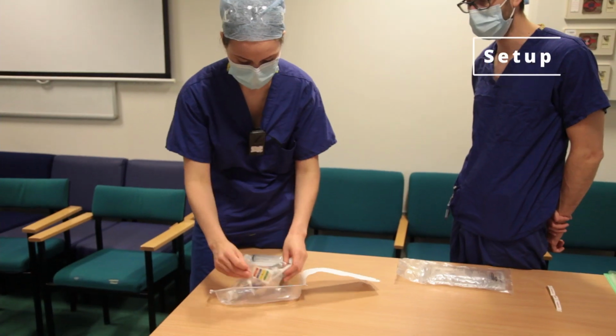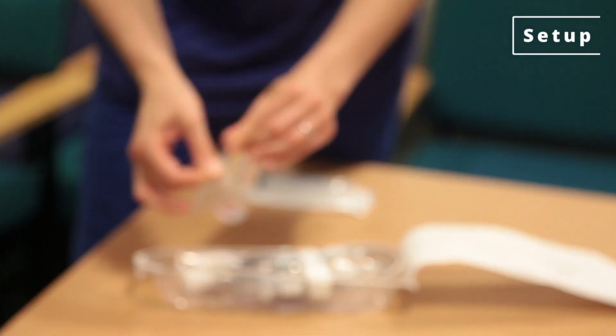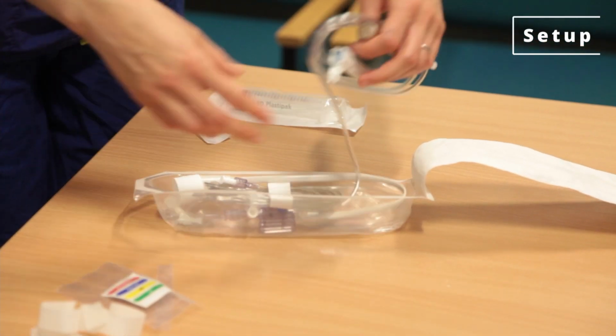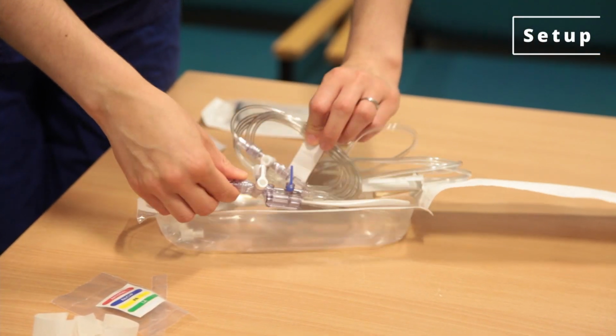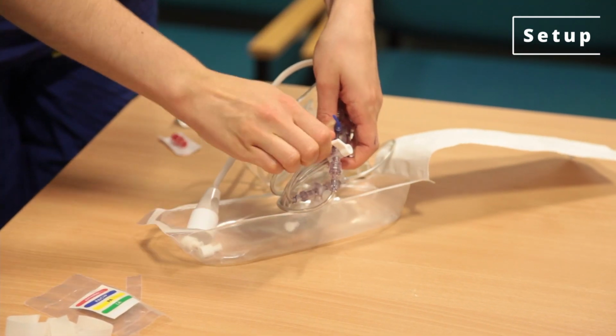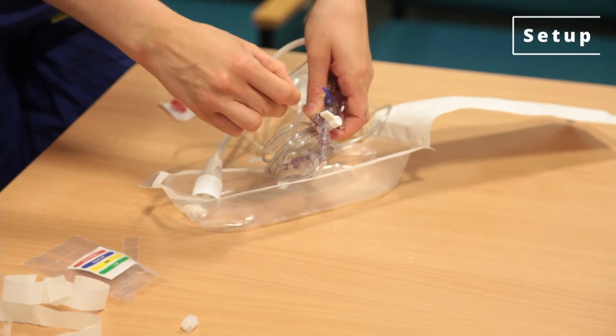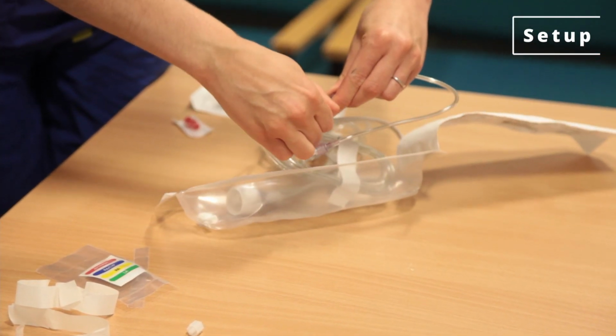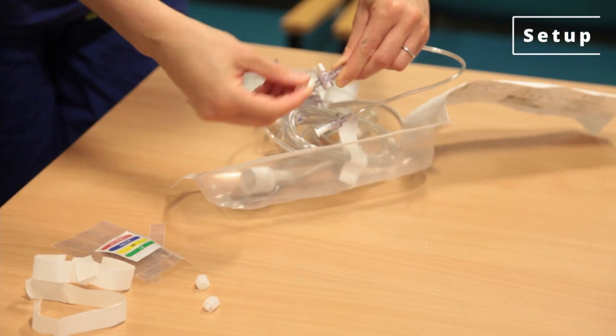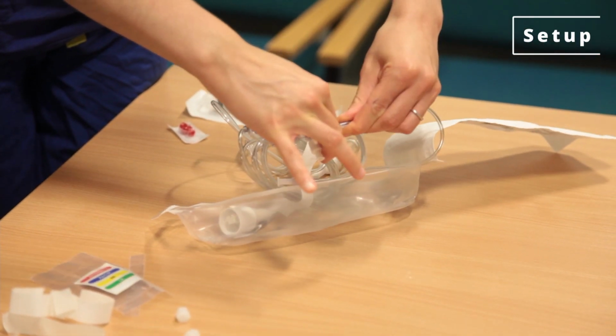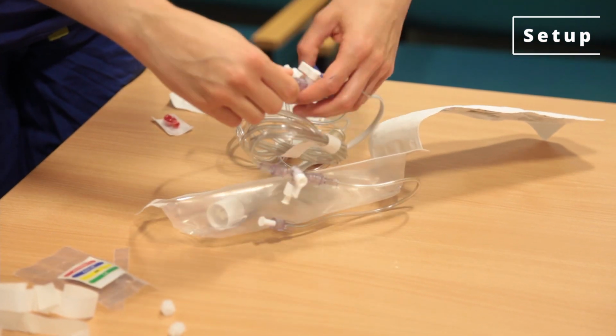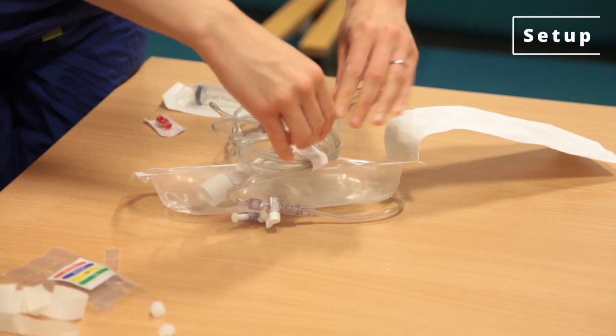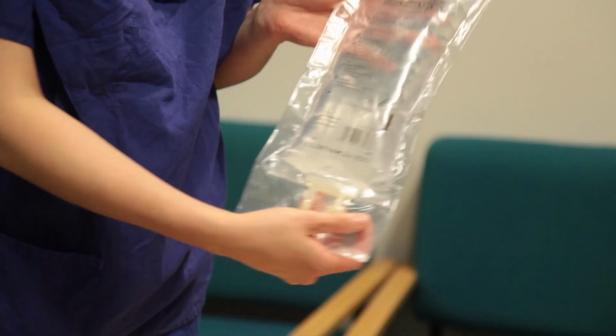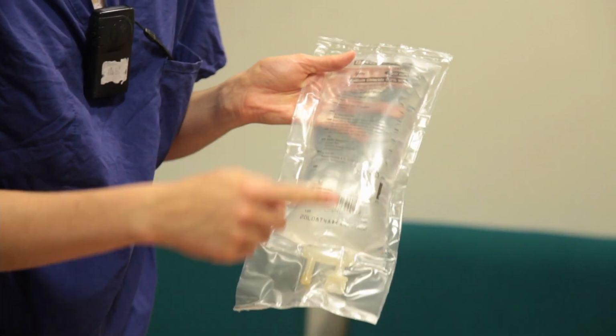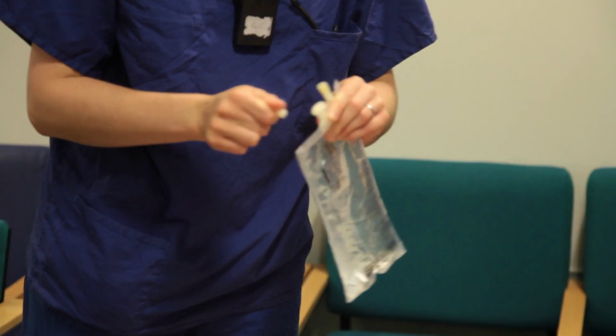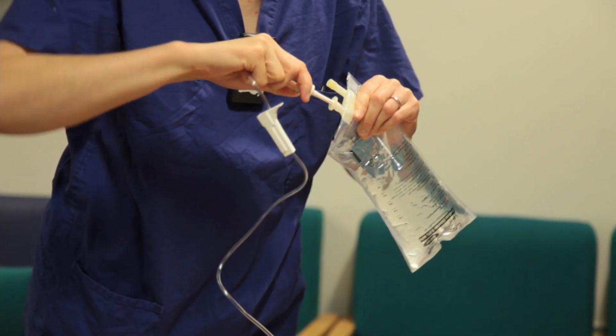In the setup process, unpack the transducer set, remove all the bungs with an open end from the ports and replace with closed-ended bungs. Ensure all connections are tight so as to avoid any air entering the system. Check the date and contents of your saline flush bag. Remove the flush bag cap and spike with the arterial transducer set.